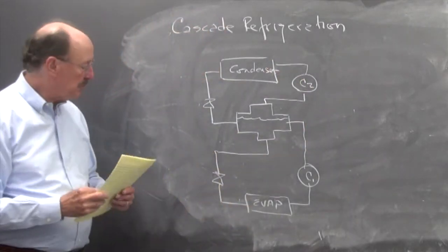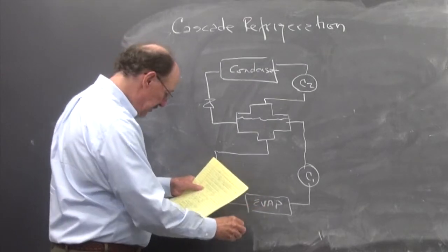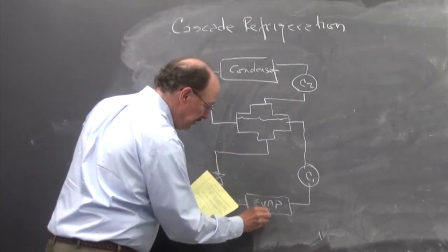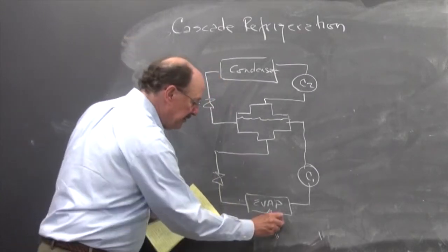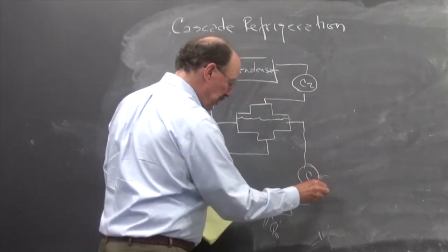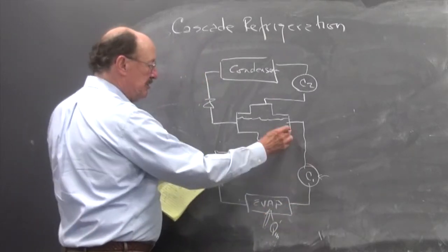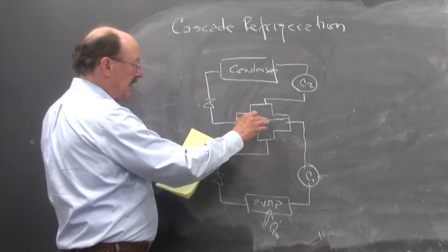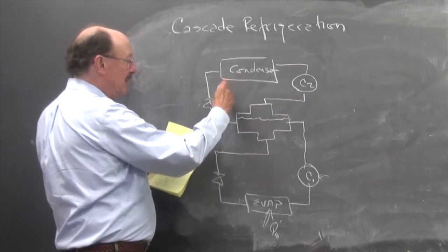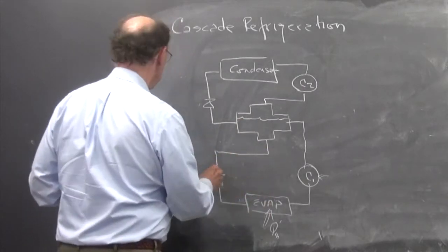So if we look at this, what's happening here is this is our low temperature heat in. Here's the Q dot into the system. Here's our compressor work coming in, so I have my power there. I'm going to discharge in this, rather than being a condenser, I have a liquid in here. It's the same refrigerant, so this is a direct contact heat exchanger.